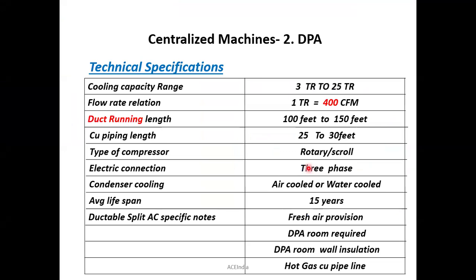Now we can see the technical specification. Typically, the cooling capacity range of these DPA machines ranges from 3 to 25 ton. Then once again, 1 ton is equal to 400 CFM. While discussing DSA, I told you the maximum duct running length should be around 60 to 100 feet. That's for a ceiling suspended unit. So for a floor mounted machine, the main advantage is the duct running length. Why? Because a normal DPA can connect up to 100 to 150 feet of duct single-handedly from a single DPA itself.